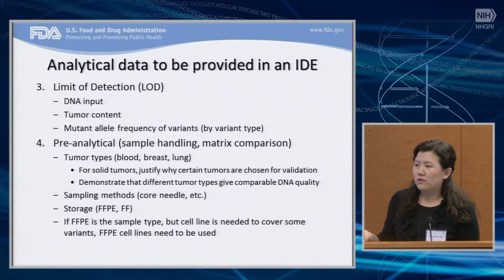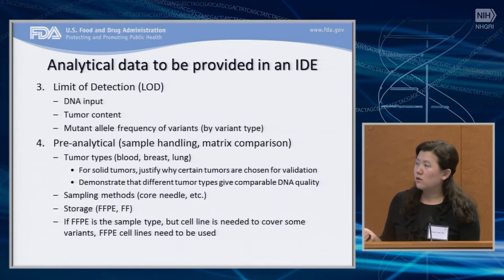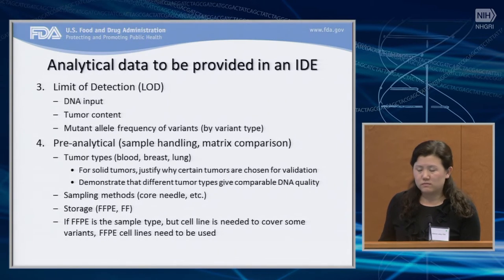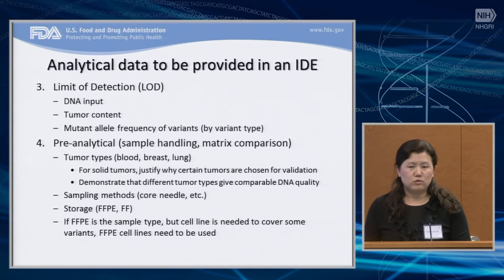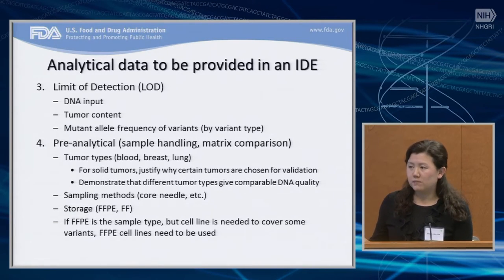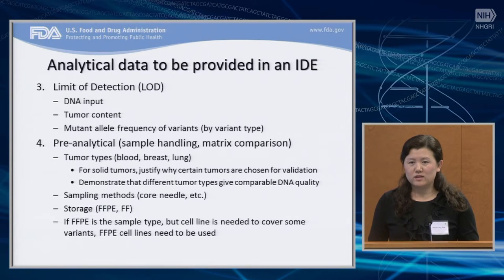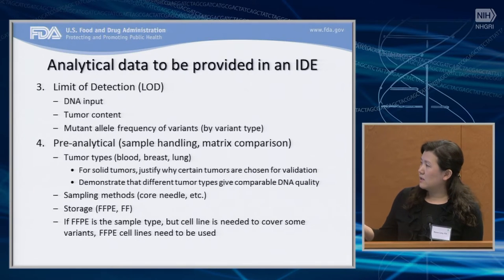Another important aspect of the analytical study for the NGS test in IDE is the limit of detection. You need to show what the minimum DNA input or genomic DNA input your device requires. For tumor content, can you detect down to 5 percent tumor in a sample? Another key metric is the mutant allele frequency of variants — for example, whether your device can detect down to 1 percent or 5 percent of SNVs. These need to be specified by different variant types. These are performance characteristics you as an investigator also want to know to confirm your device is accurate and reliable by different users.